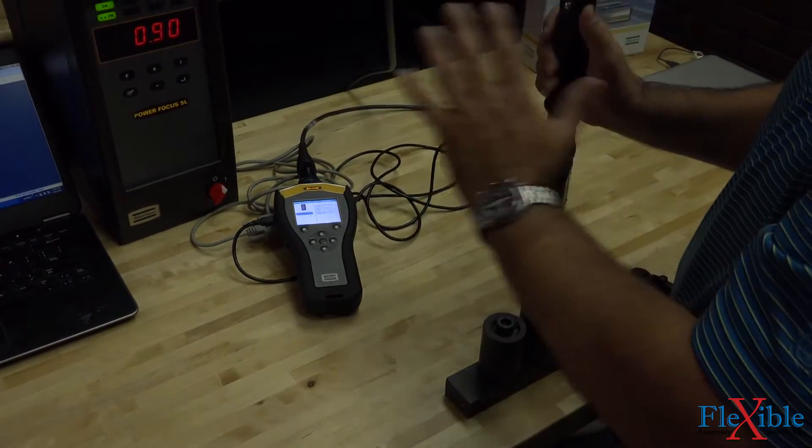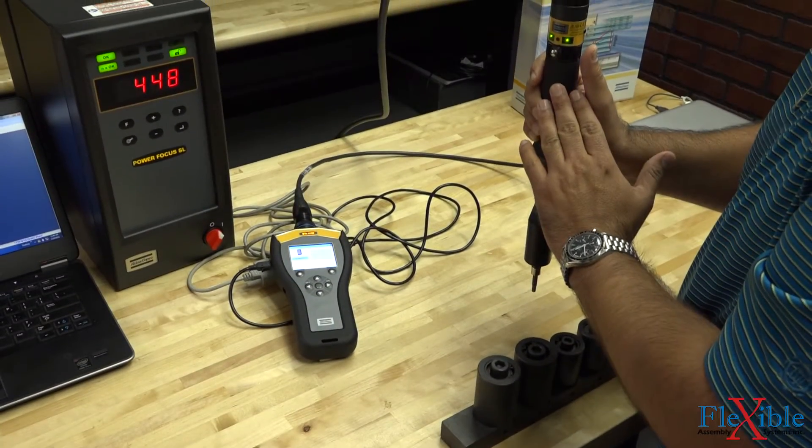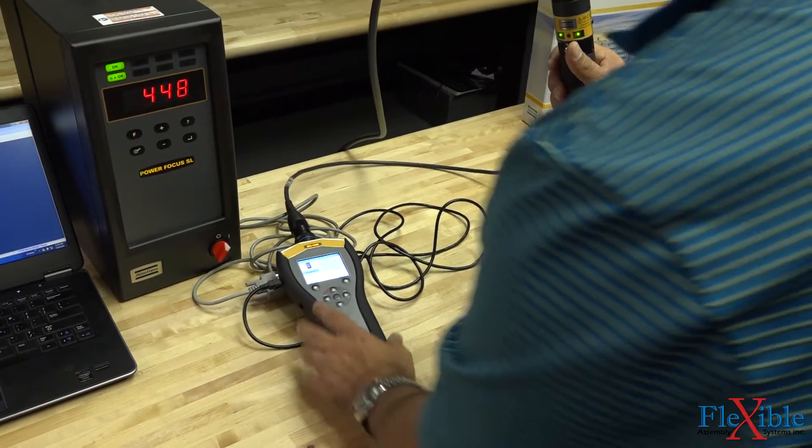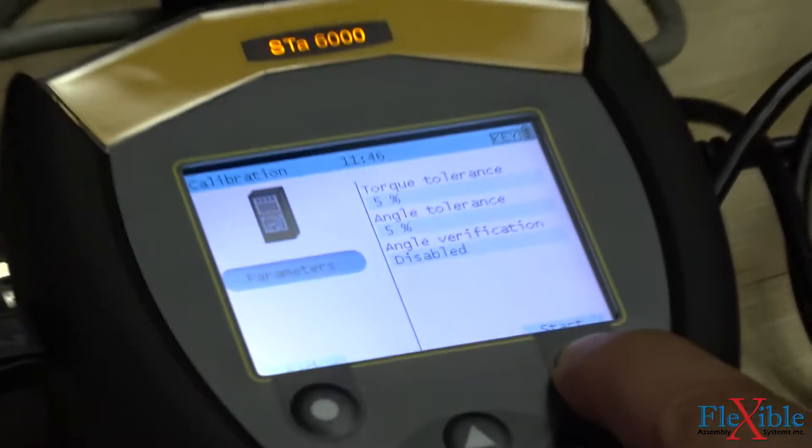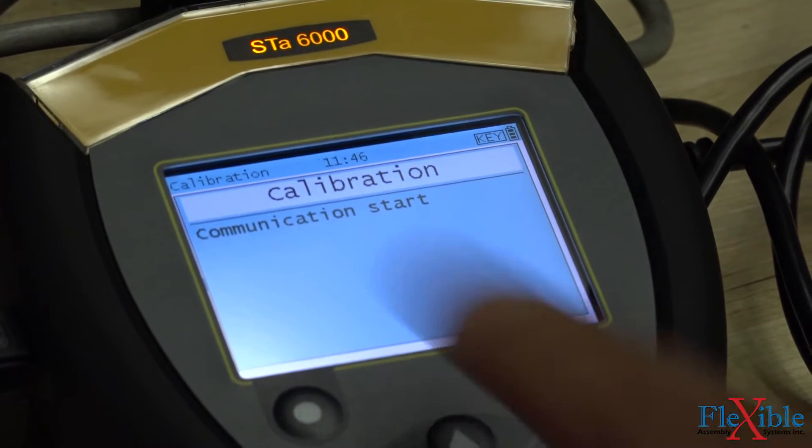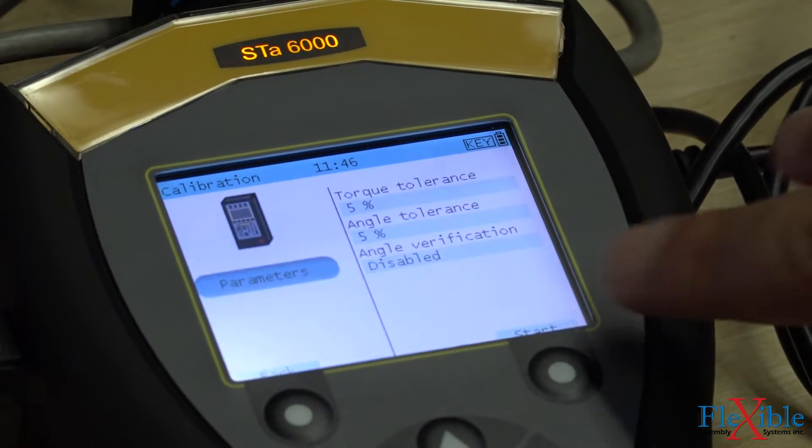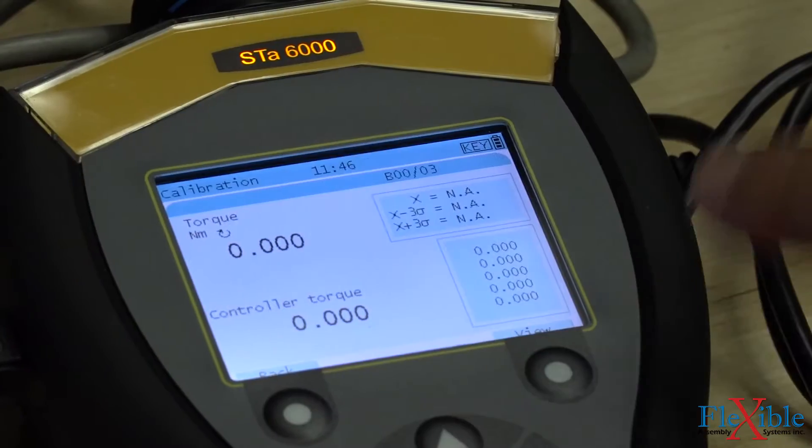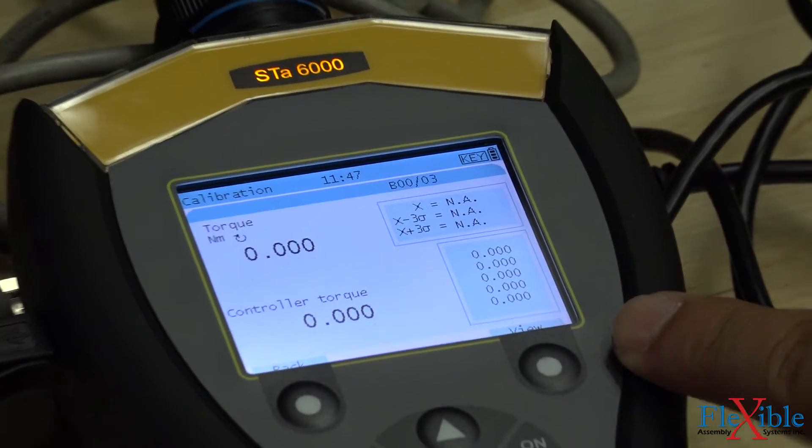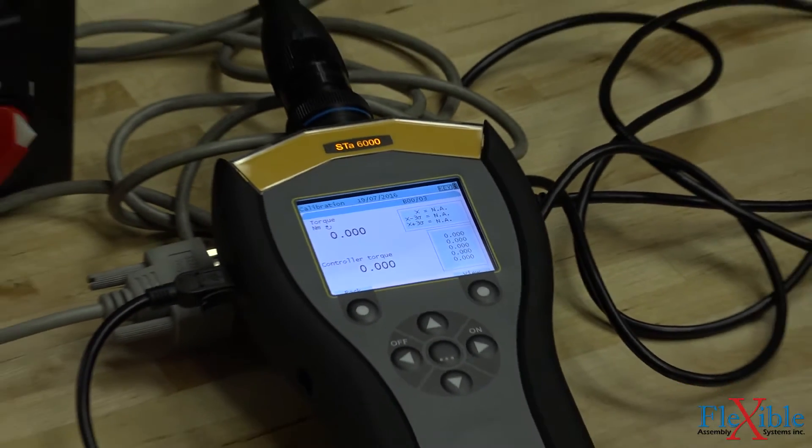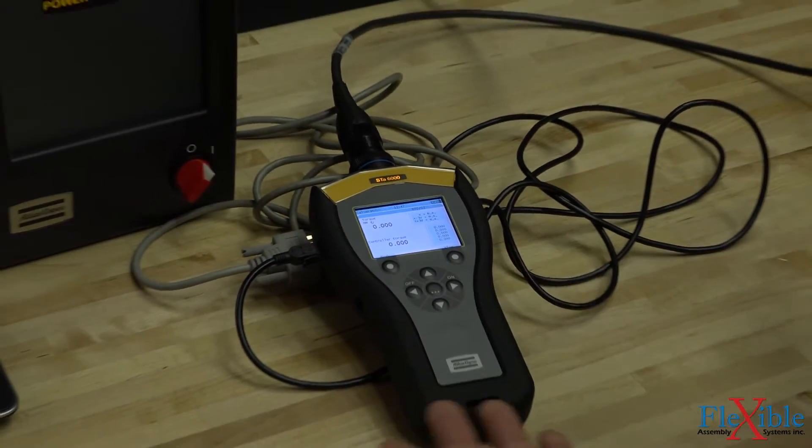Now no matter what controller we use, this tool will remember its calibration value. Let's run the calibration one more time. Again, we hit start to repeat the process. The analyzer will automatically use the same PSET as before. If you wish to change the PSET, you must select it before starting a new test. We will now perform another three rundowns.